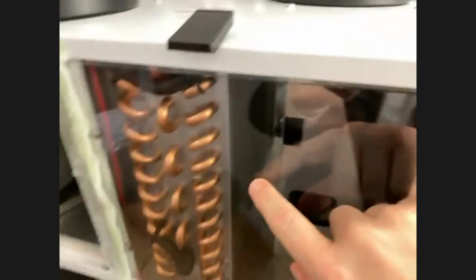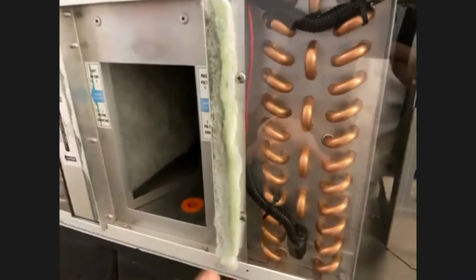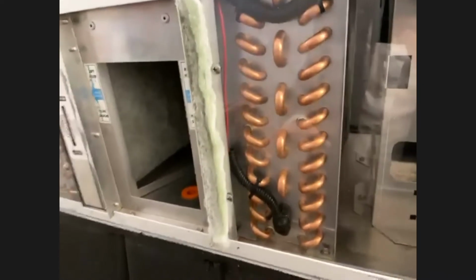Meanwhile, I still have fresh air entering the unit here. But because the damper is like this, the air is crossing the coil and is going back outside. Usually that coil and the compressor would be in a box outside. If you have a regular mini split, that coil and the compressor would be in the box outside. But we cleverly brought those components inside the box, meaning that you don't have to pass refrigerant lines whatsoever, okay, to have something extremely compact to do a great job.